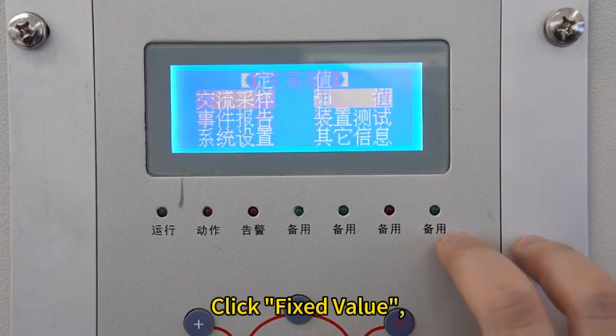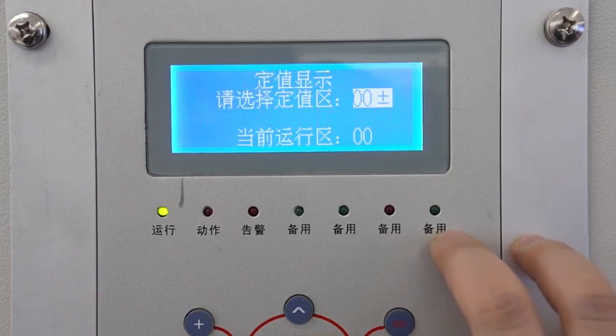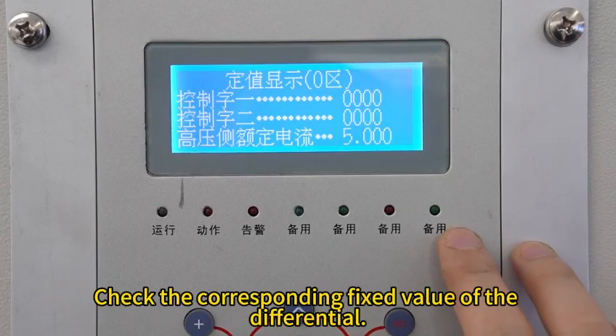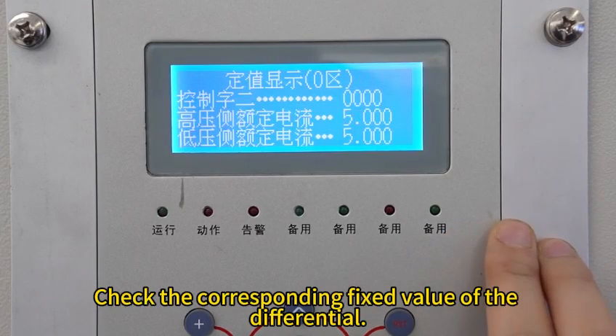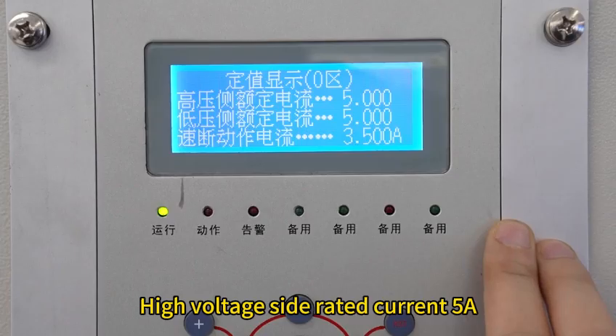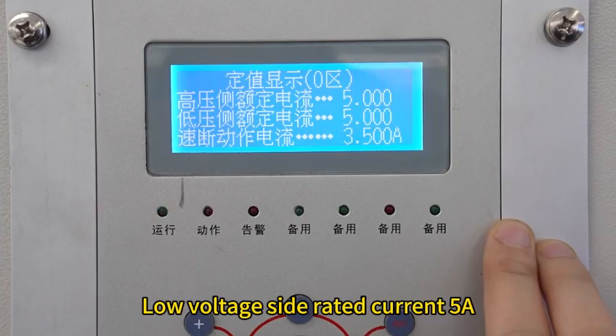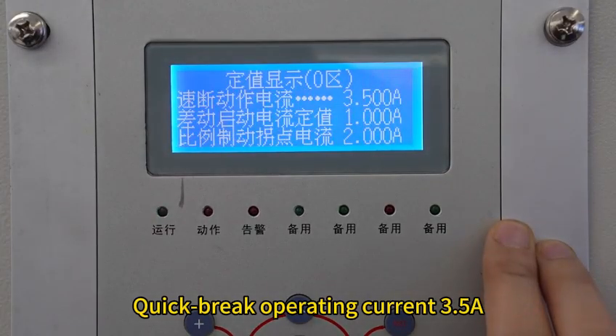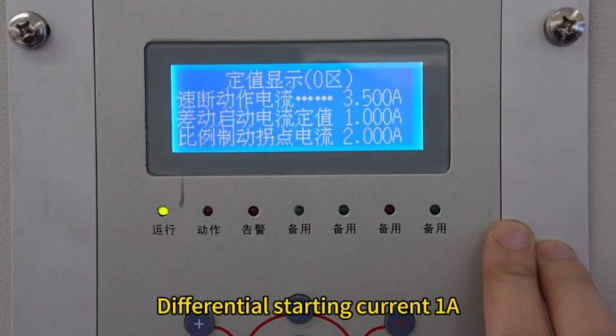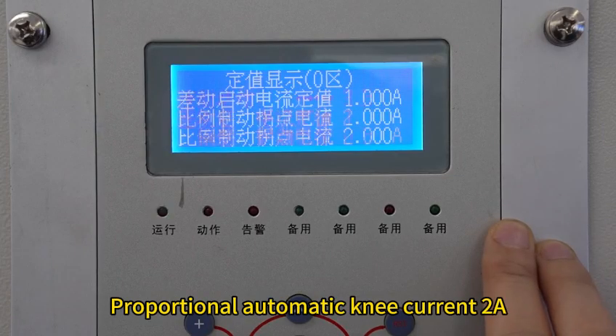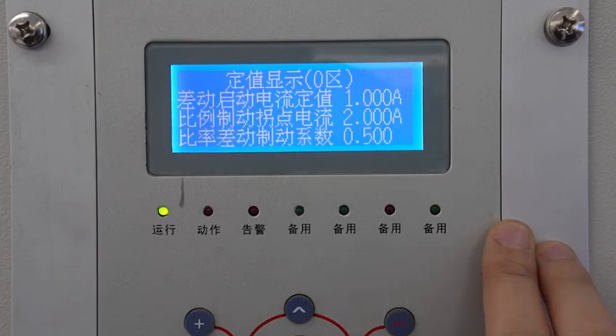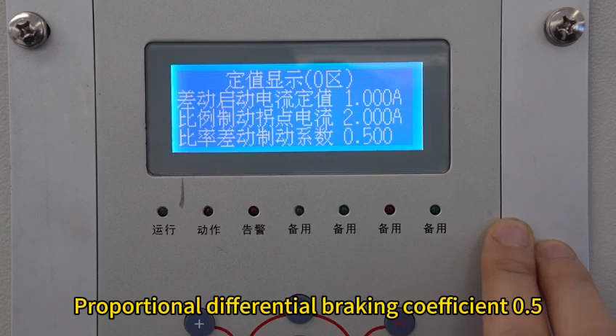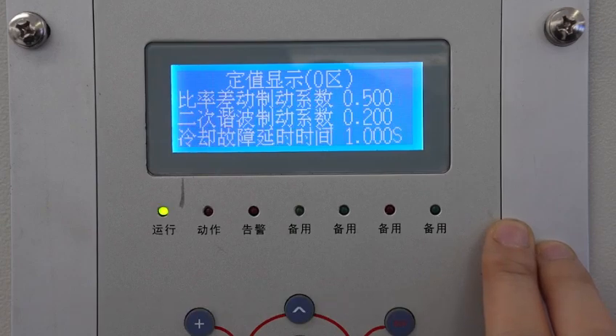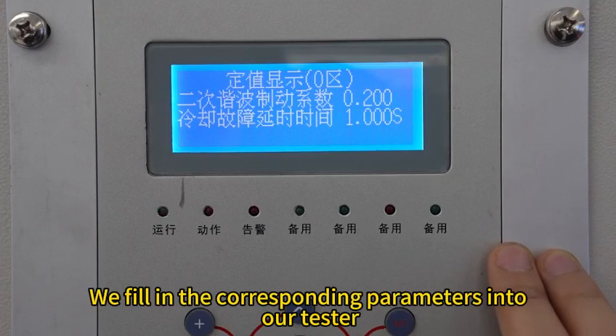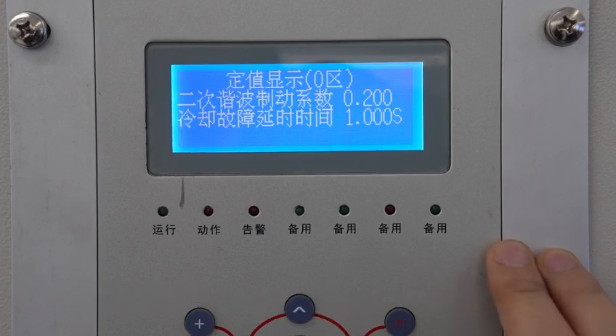After starting the tester, we first enter the settings page of the differential protection device. Click Fixed Value, Display, and OK in sequence. Check the corresponding fixed value of the differential. High voltage side rated current 5 amperes. Low voltage side rated current 5 amperes. Quick break operating current 3.5 amperes. Differential starting current 1 ampere. Proportional braking knee-point current 2 amperes. Proportional differential braking coefficient 0.5. We fill in the corresponding parameters into our tester.